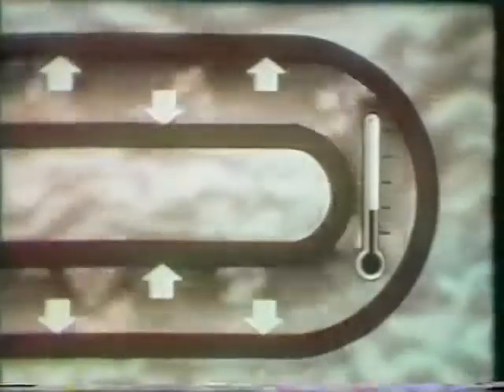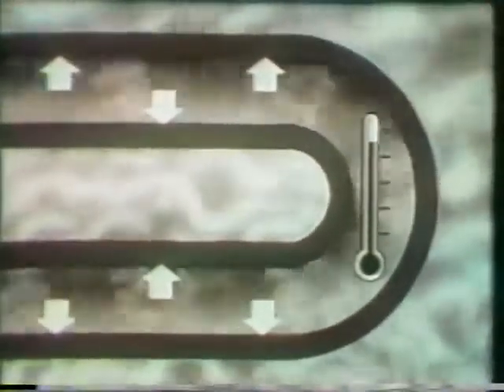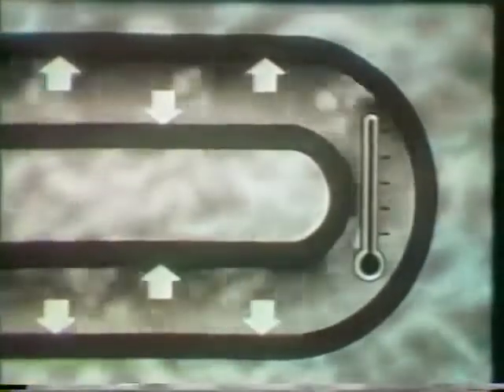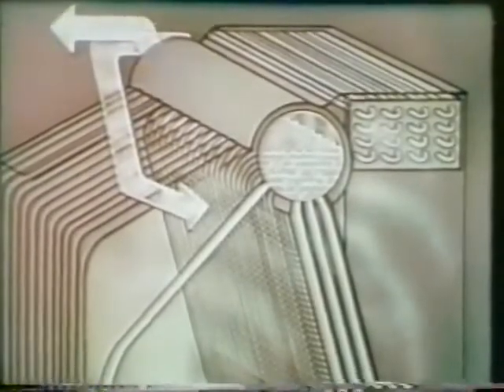However, if the saturated steam is taken out of contact with the boiler water by being sent to a separate bank of tubes, the superheater, the temperature of the steam can be raised without an increase in pressure. The result is superheated steam: steam that has approximately the same pressure as the saturated steam, but a higher temperature. Note that the steam used for auxiliary machinery is drawn directly from the steam drum, since such steam does not have to be superheated.